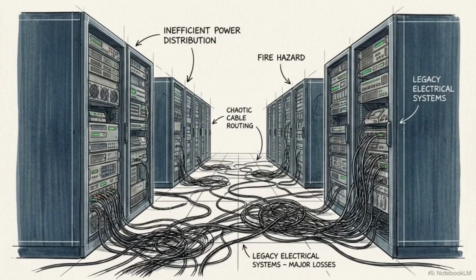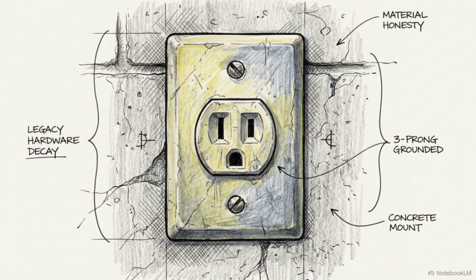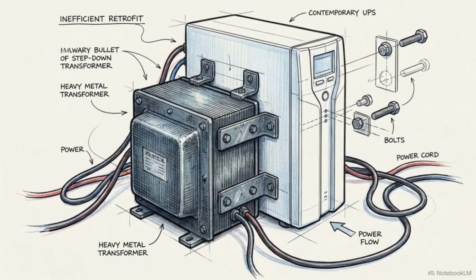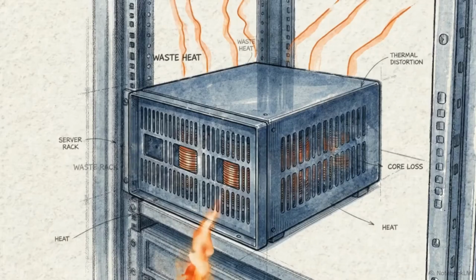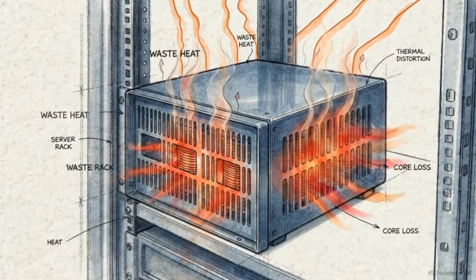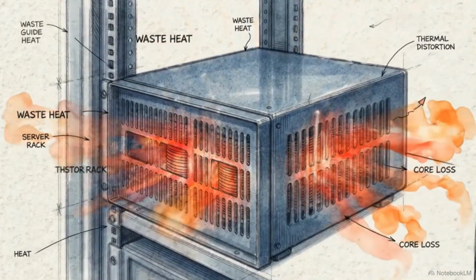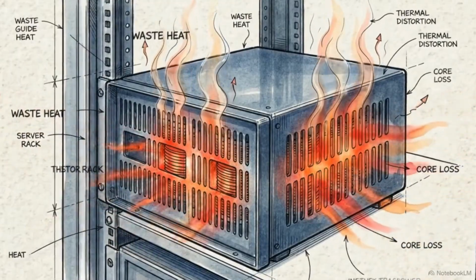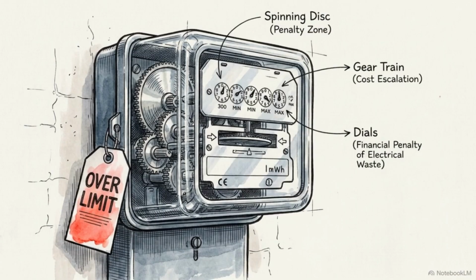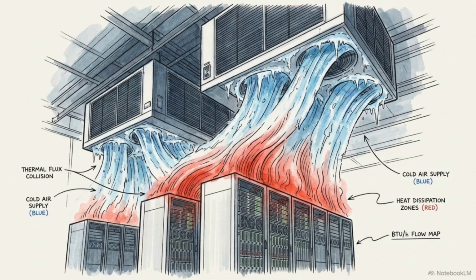We also have to consider the efficiency of how power is delivered to the rack. North American server closets have relied on the 110-volt standard for decades. To support larger deployments on these legacy circuits, organizations often bolt step-down transformers onto their UPS systems to accommodate 110-volt cords. These transformers experience core and copper losses, bleeding 3 to 7% of their electrical load as pure waste heat. This creates a double financial penalty. You pay for the wasted electricity, and then you pay for the additional air conditioning required to cool the heat the transformer radiates into the rack.